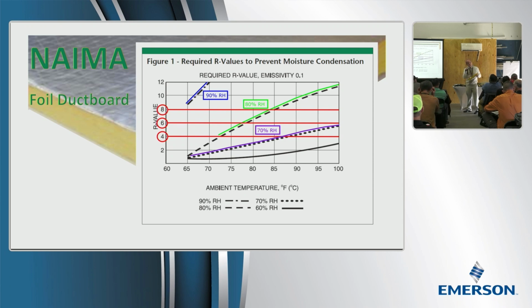And some of the stuff that's on there is specifically about what to anticipate with regard to whether the duct is going to sweat. Well, the bottom line is the people that sold you this, that made it, they told you it was going to sweat. So you can't be surprised that it's sweating because they said it would. And here's where they told us, if you put that stuff in a place where the relative humidity is 90% for any reason at all, it's going to sweat. And it doesn't matter if you use R8, R6, R4, it's not going to matter.